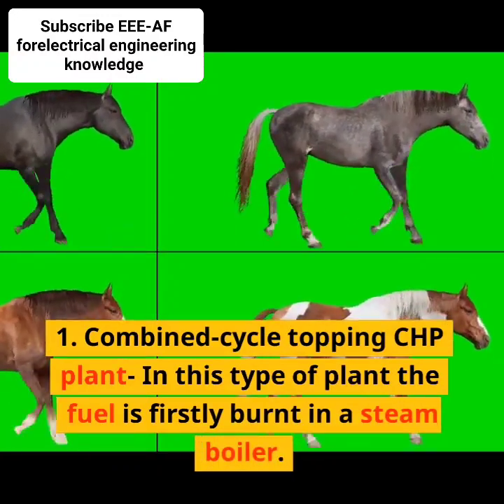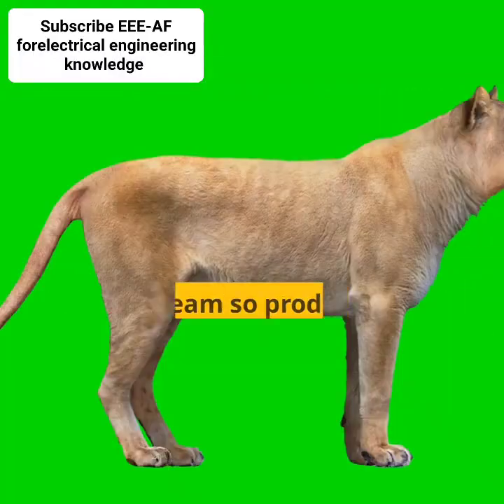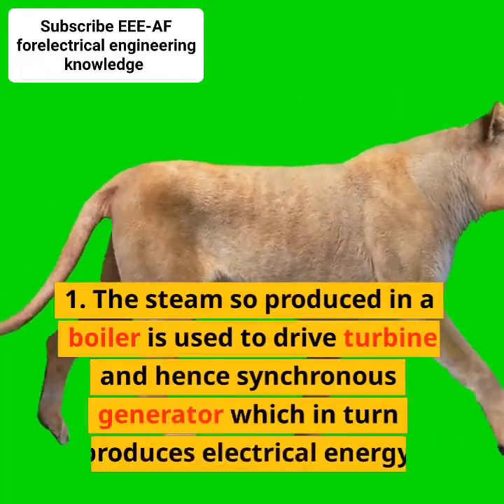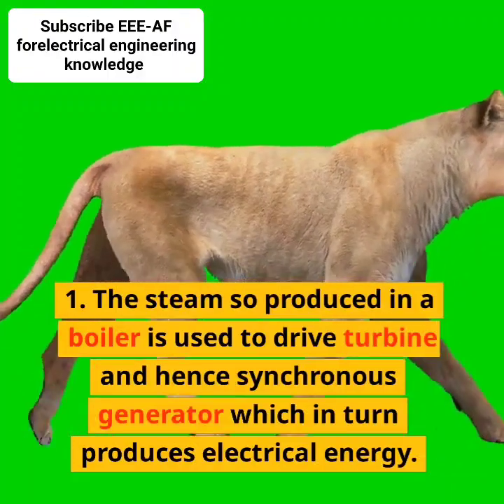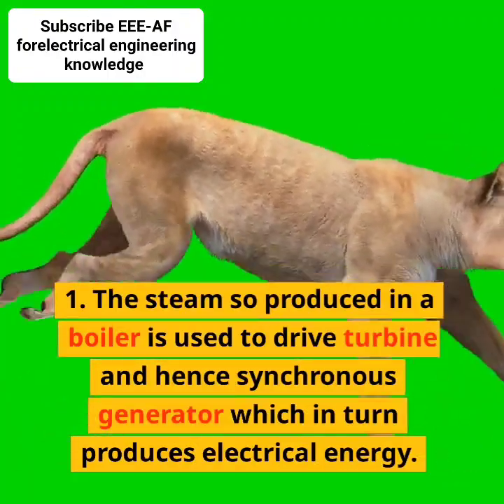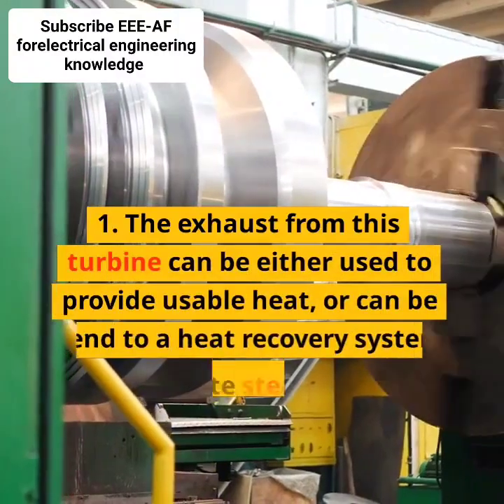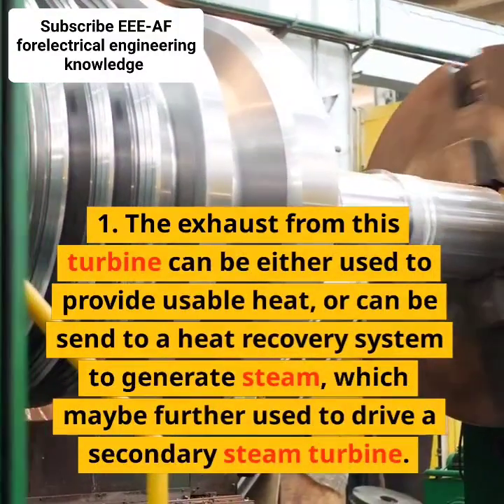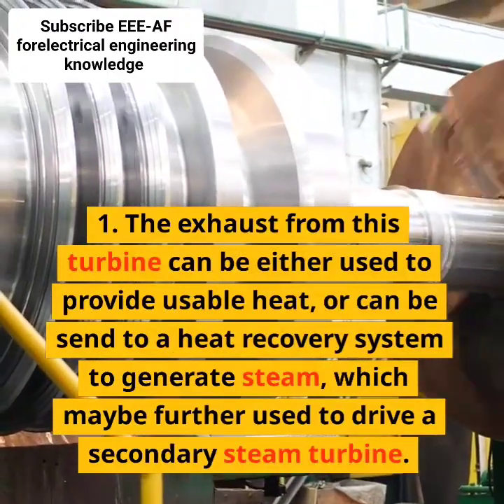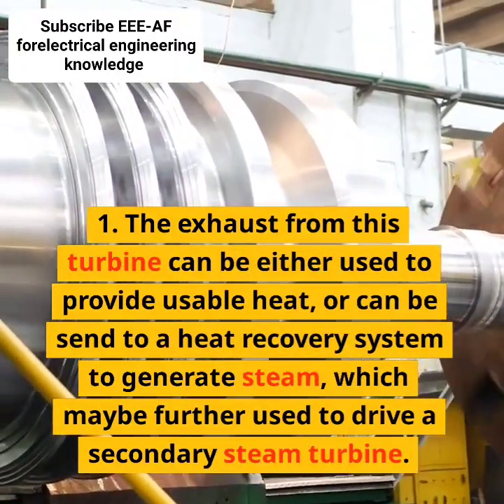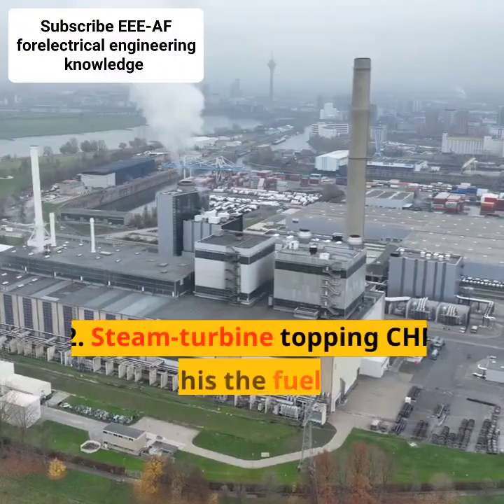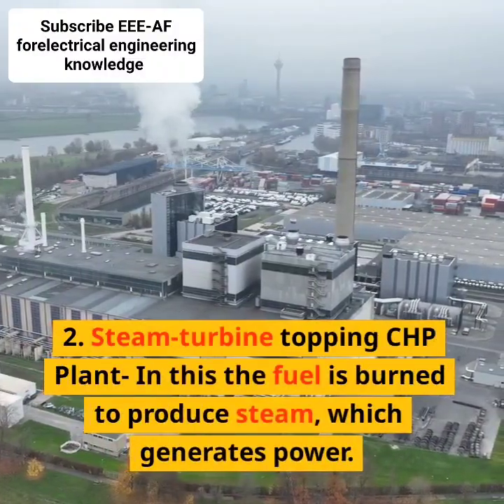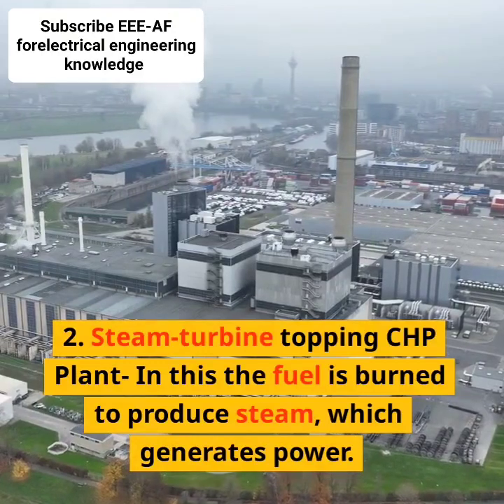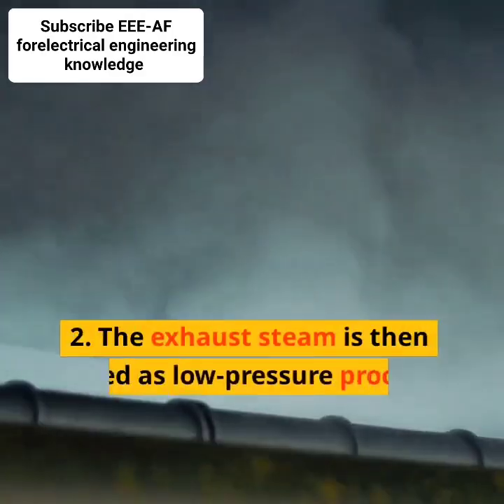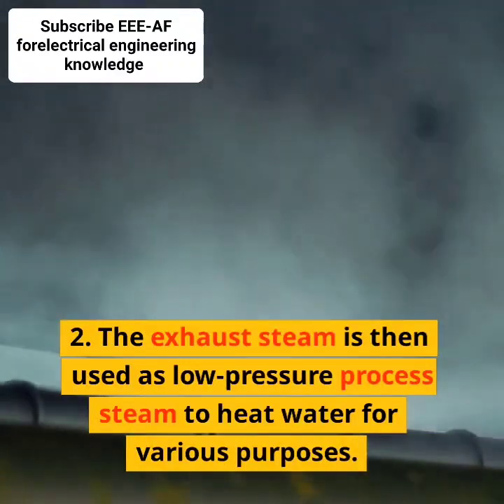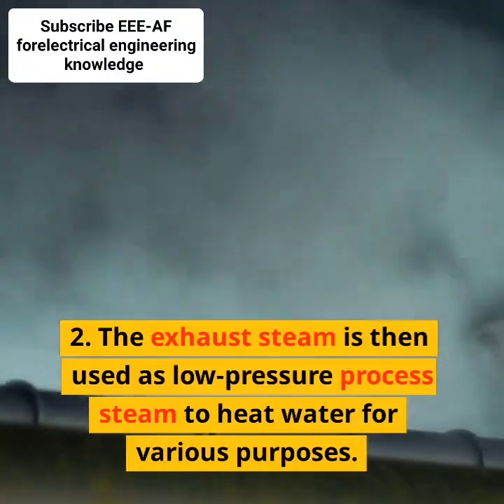In this type of plant, the fuel is firstly burnt in a steam boiler. The steam so produced in the boiler is used to drive a turbine and hence a synchronous generator, which in turn produces electrical energy. The exhaust from this turbine can be either used to provide usable heat, or can be sent to a heat recovery system to generate steam, which may be further used to drive a secondary steam turbine. 2. Steam turbine topping CHP plant. In this, the fuel is burned to produce steam, which generates power. The exhaust steam is then used as low-pressure process steam to heat water for various purposes.